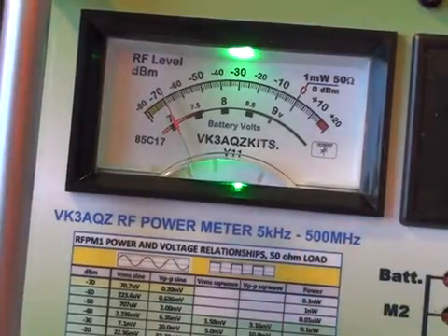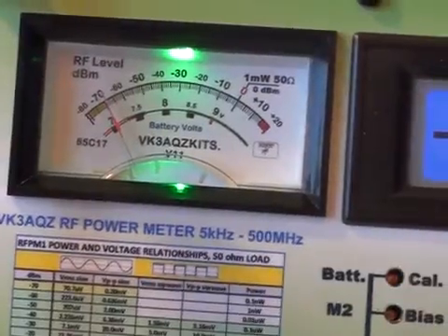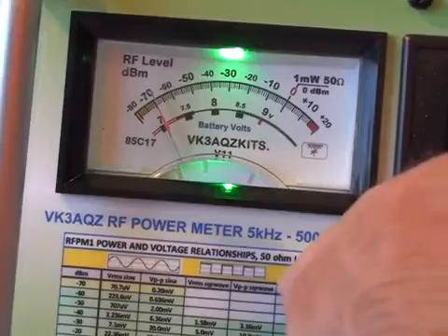There is a small UHF boost circuit in the RF detector head, which helps flatten the response above 300 MHz.